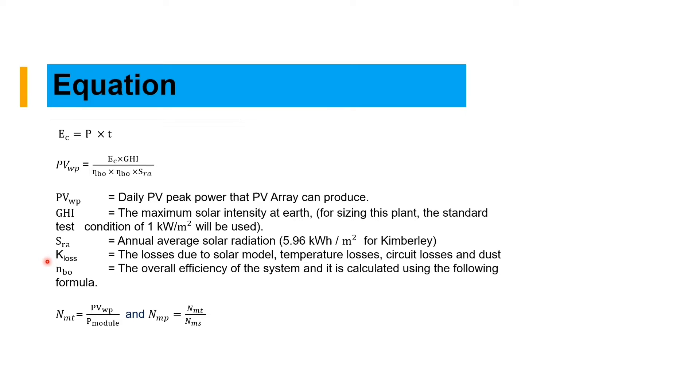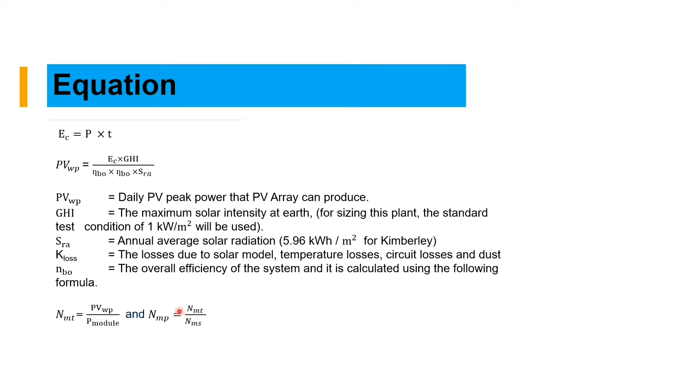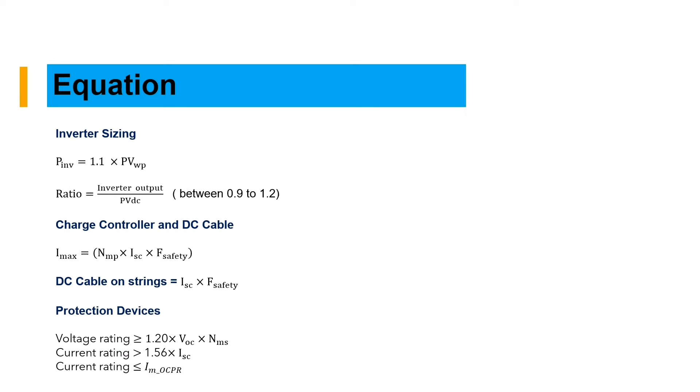We have the total number of panels, which is equal to the PV array divided by the power of the module that we are using. And the total number of panels in parallel is equal to the total panels divided by the number of modules in series.